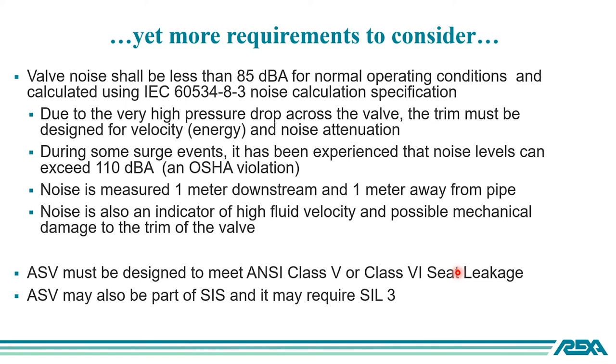A few more points to consider, of course, are that you typically want this valve to be less than 85 decibels. Because there is a lot of flow and it's going through a very restricted orifice, high velocities could create huge levels of noise, right? And you want to make sure that your trim is designed so that that noise is attenuated to less than 85 decibels, right?